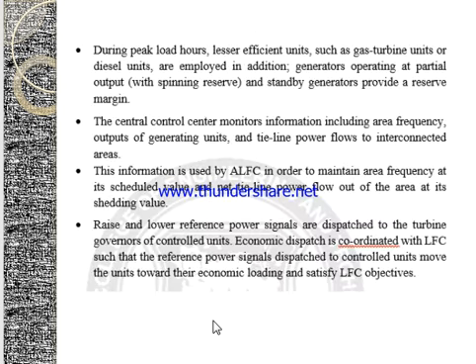The CEDCs are provided at the central control centers while the variable part of the load is carried by units controlled from the central control center. During peak load hours, lesser efficient units like gas turbine units and diesel units are employed in addition. Generators operating at partial output and standby generators provide a reserve margin. The central control center monitors area frequency, outputs of generating units, and the tie-line power flows between interconnected systems. All this information is used by the ALFC to maintain area frequency within a scheduled time period. Raising or lowering of the reference signals are dispatched to the turbine governors of the controlled units, and the economic dispatch is coordinated with LFC so that units move toward their economic loading while satisfying load frequency control objectives.